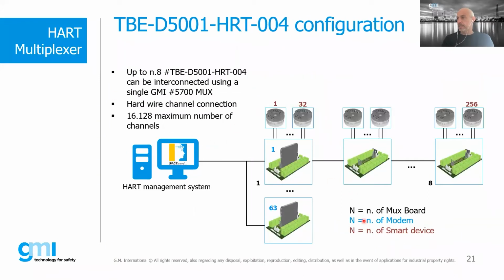And this is the other application, where you don't use isolators, but just connect the transmitters to the termination boards, in and out. The architecture is the same. In this case, for 256 channels you have up to 8 termination boards, with just one HART multiplexer for one node. The 63 is, of course, the number of nodes you can connect to just one HART management software. More than 16,000 channels can be connected in this architecture.